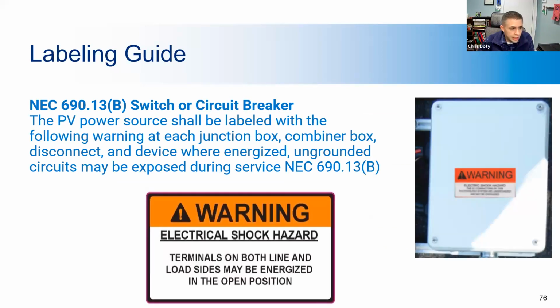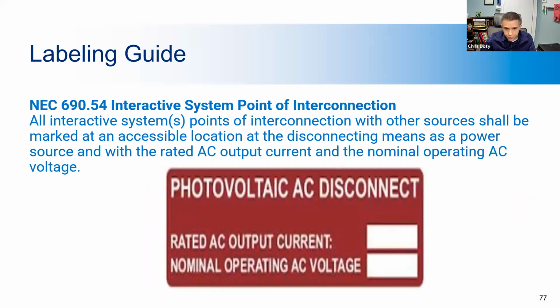Here you have the electrical shock hazard sticker. You want to have this on all your switches and circuit breaker panels as well, so people understand there's a hazard and to be careful. Anytime you have an inverter output, that's known as an interactive system point of interconnection, and you have to label it with the rated AC output current and the nominal operating voltage.